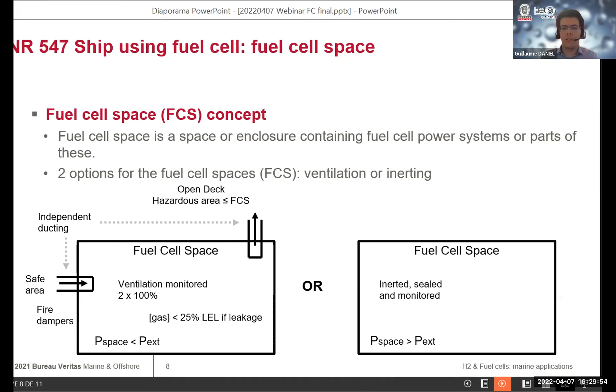And the fuel cell space is the casing, the room that will be able to contain the gas. And all this - most of the requirements, most of the strategy, the safety strategy - will apply to this space. So it's very important to define it very well at the very beginning. And you have two possible strategies: you can either ventilate that space, kind of prescriptive, or inert it, also with specific rules on this. So this concept is pretty important.